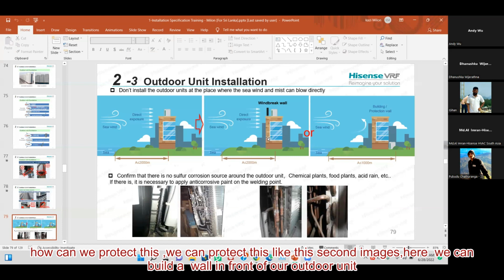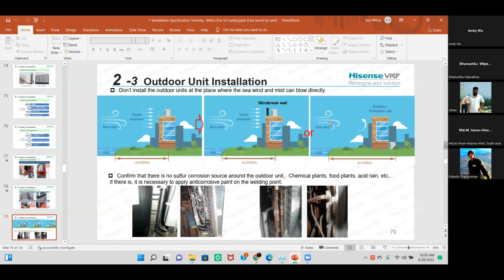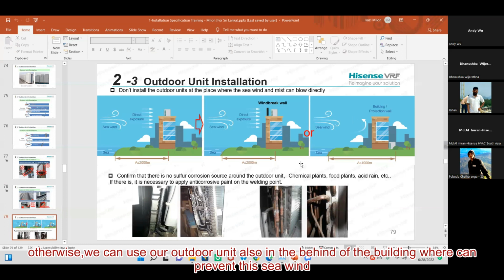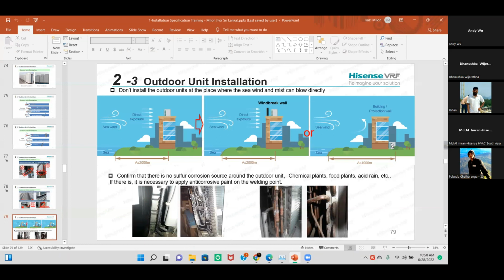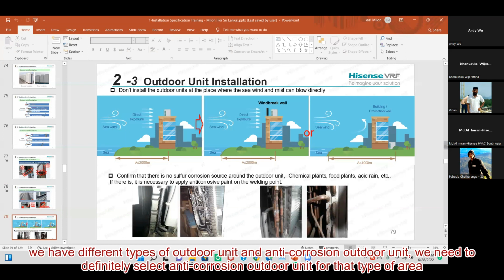We can protect it like in the second image. We can make a barrier wall in front of our outdoor unit, so the sea wind cannot directly hit it. Otherwise, we can place the outdoor unit behind the building to protect it from the sea wind. In these types of environment, we have anti-corrosive outdoor units, and we definitely need to select them for these areas.